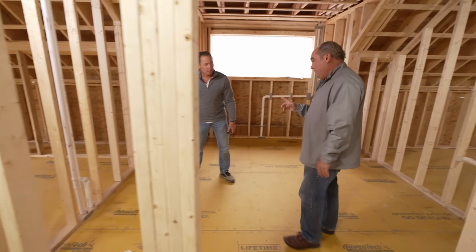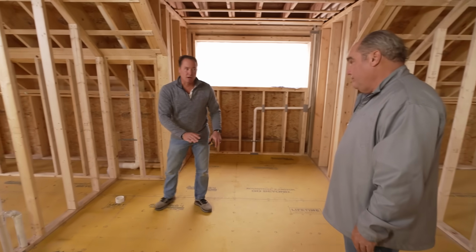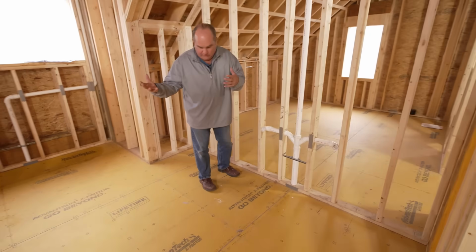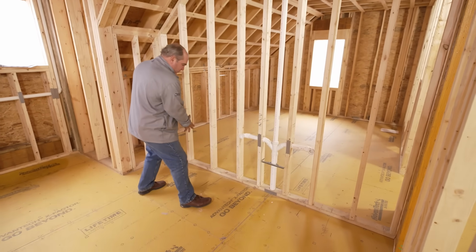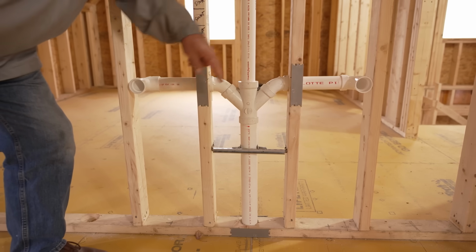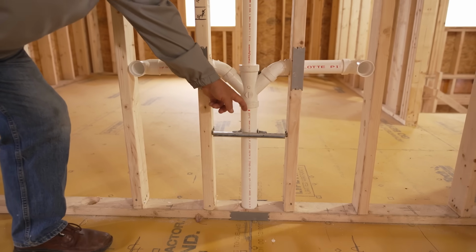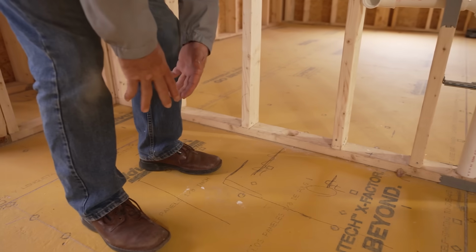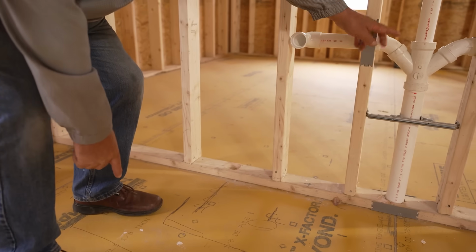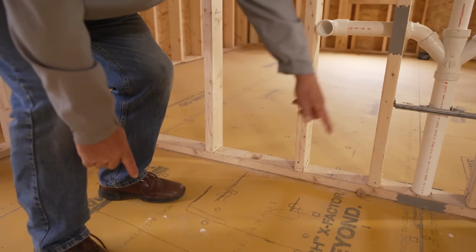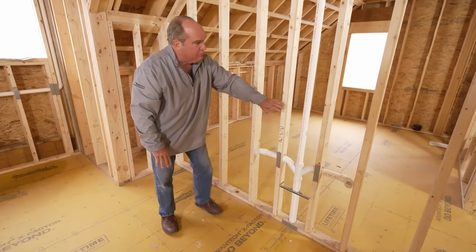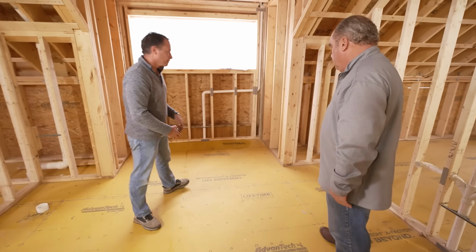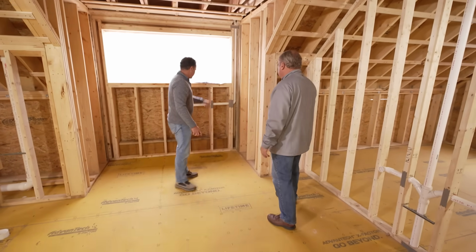Okay. So normally you'd wet vent that, right? Yep, but because I couldn't get across, that wasn't happening. All right, so by definition, a wet vent, which is a standard component for plumbers, is normally there might be a toilet here, and these are the lavatories. And from this point down would be the drain. It would come down here into the branch where the toilet might be. So this pipe between here and here would let water go this way, but also would double as the vent for both the toilet and the fixtures, and that would be called a wet vent this way, and you couldn't do that. Nope. So individual drain to the tub, individual vent up, which was another obstacle.